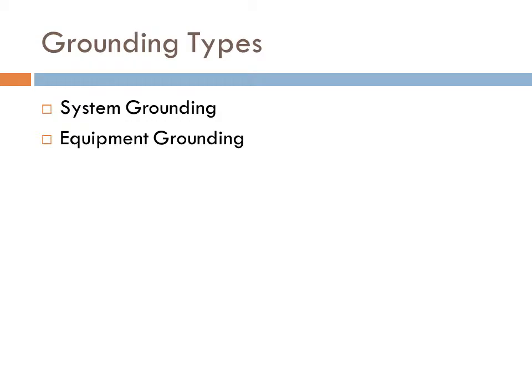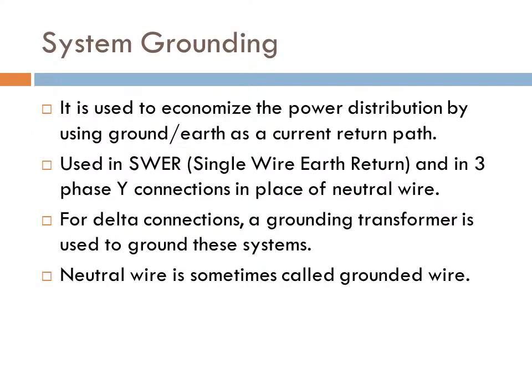Types of grounding. There are two types of grounding: system grounding, equipment grounding. System grounding is used to economize the power distribution by using ground as a current return path. It is used in single wire earth return, and in three phase it is used in wye connection in place of neutral wire, while in delta connection it cannot be used directly. So a grounding transformer is used to ground this system. Neutral wire is sometimes called ground.